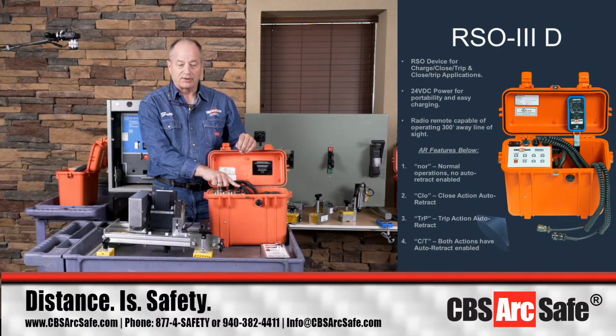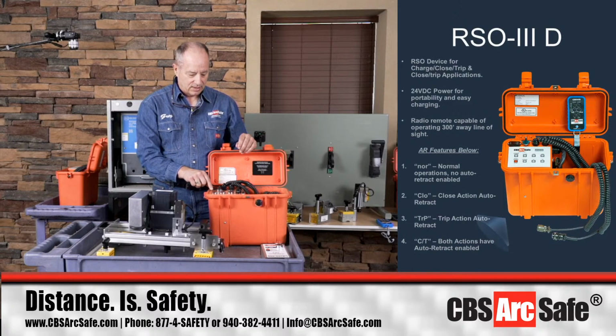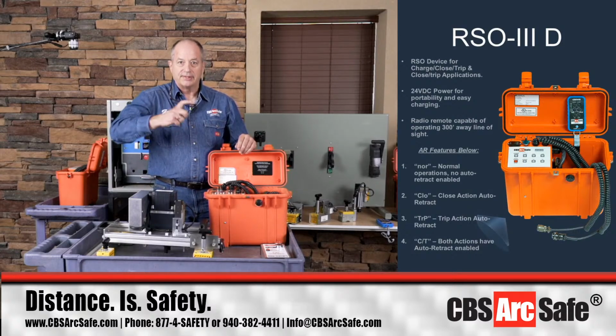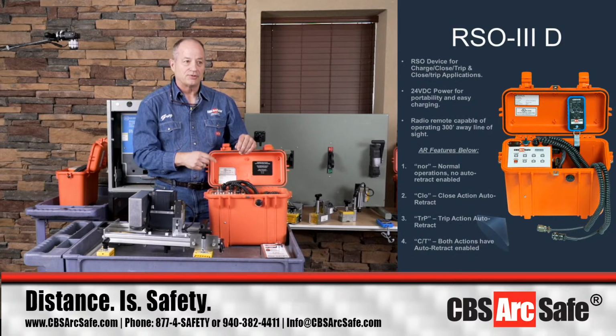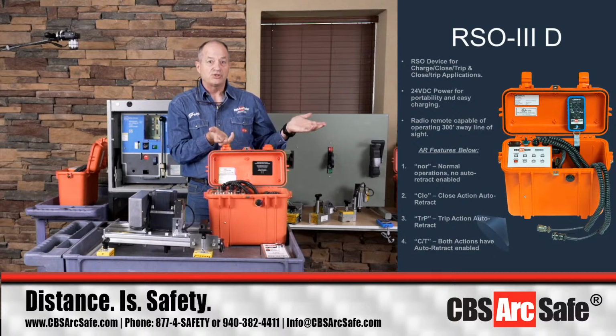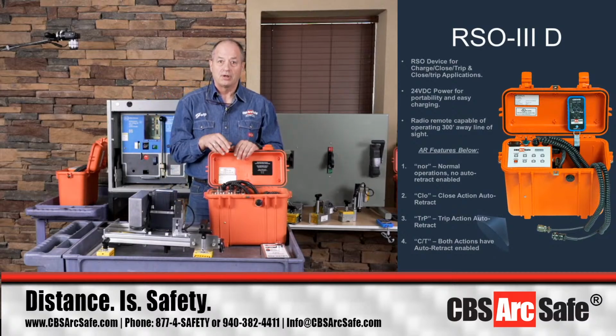And if you were to look at our old system here, you could only get 10 cycles for charging a breaker. A Square D SE breaker takes 24 cycles to charge. So you'd have to come over here and hit the charge close button 3 different times, and it would go through the 3 sets of cycles before the breaker spring was finally charged so that you could close or trip the breaker. So we said, we've got to fix this.